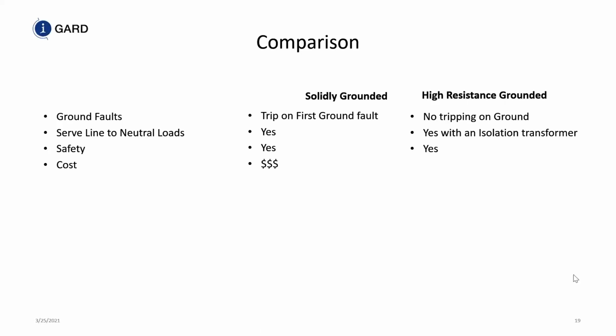The cost of a solidly grounded system, I have this question all the time. Is it cheaper to put in a resistance grounded system or a solidly grounded system? So the cost of a solidly grounded system is higher initially, because you have the cost of the 3-phase 4-wire system, that 4th wire, running the installation, running the cables for that 4th wire, putting in the G function of the LSIG. All that adds up when less than 10 to 15% of your load is going to be single phase with the distributed neutral. Why do you have to run all those conductors for 15% of your load being 3-phase 4-wire? Instead, you could put in an isolation transformer and probably end up with a less cost.